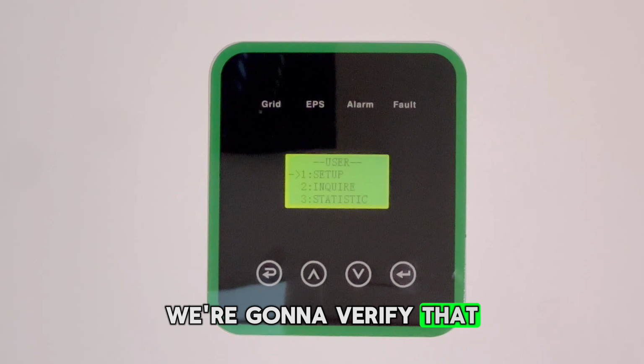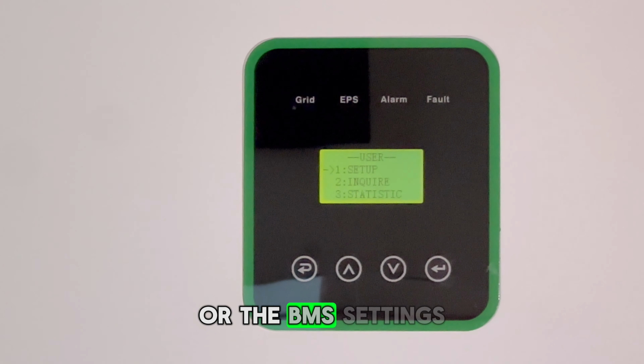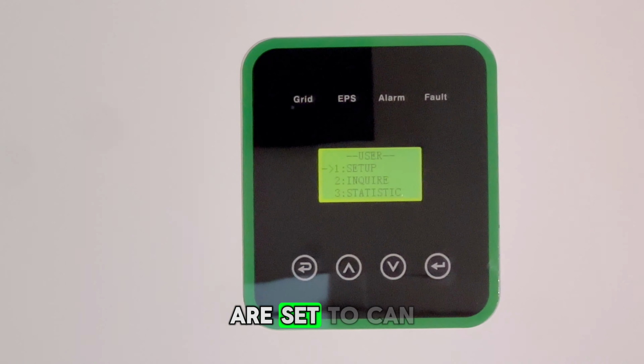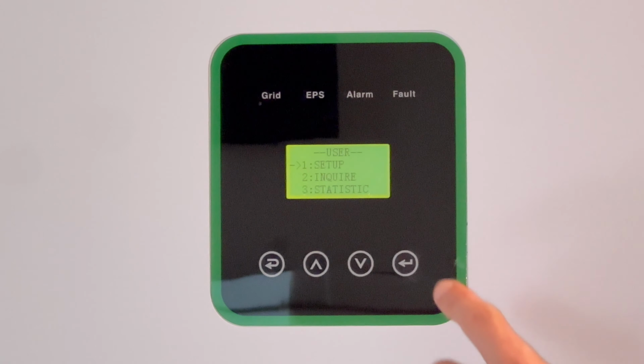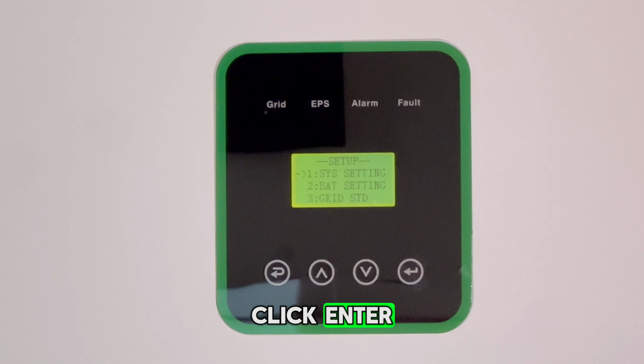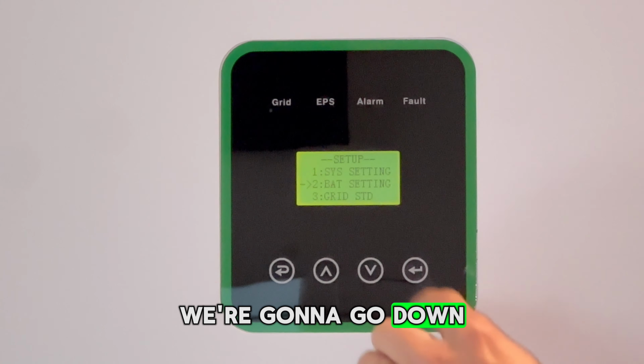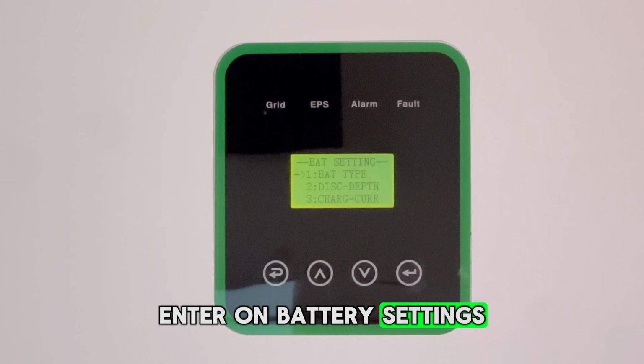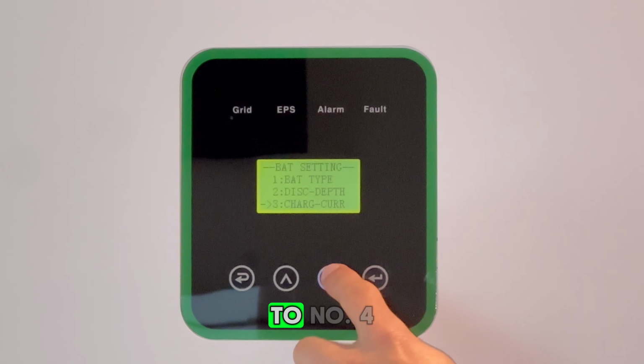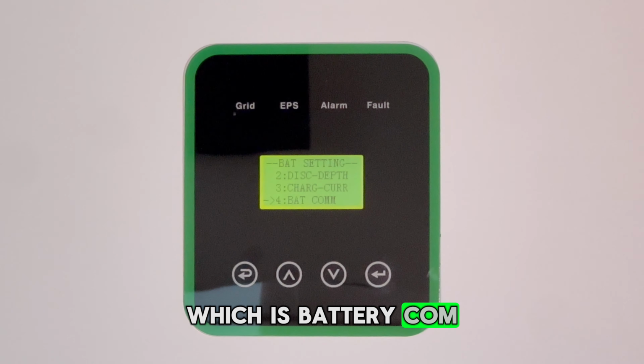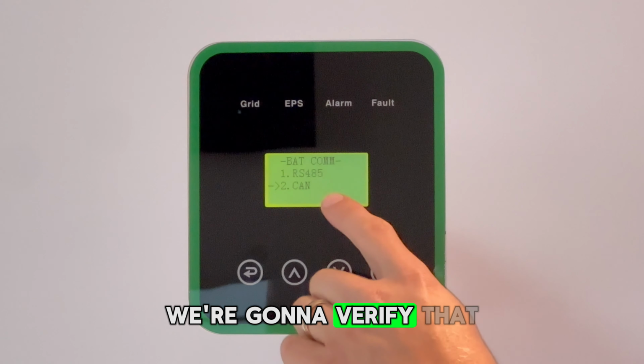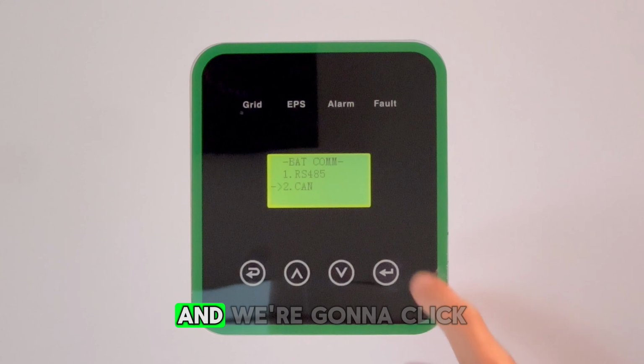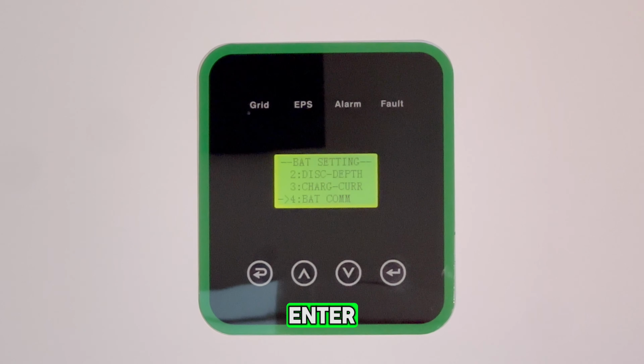We're going to verify that the battery management system, or the BMS, settings are set to CAN. In setup, we're going to click enter. We're going to go down, enter on battery settings. We're going to go down to number 4, which is battery COM. We're going to verify that it's set to CAN, and we're going to click enter.